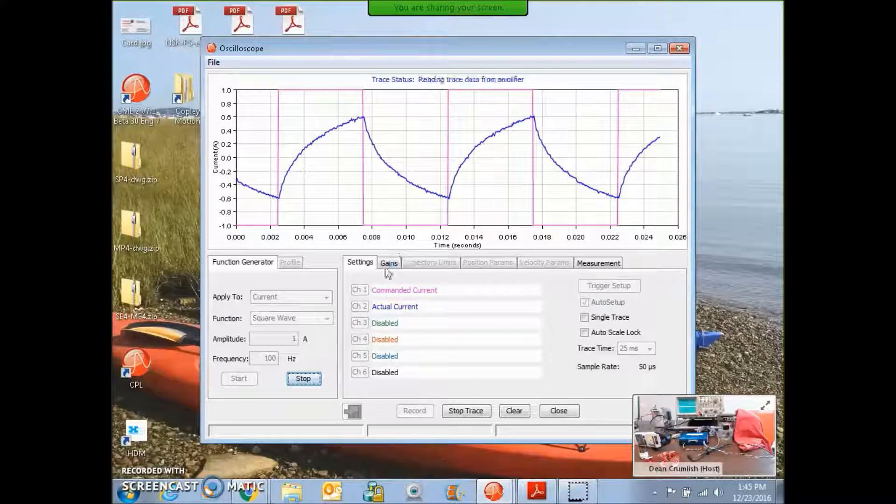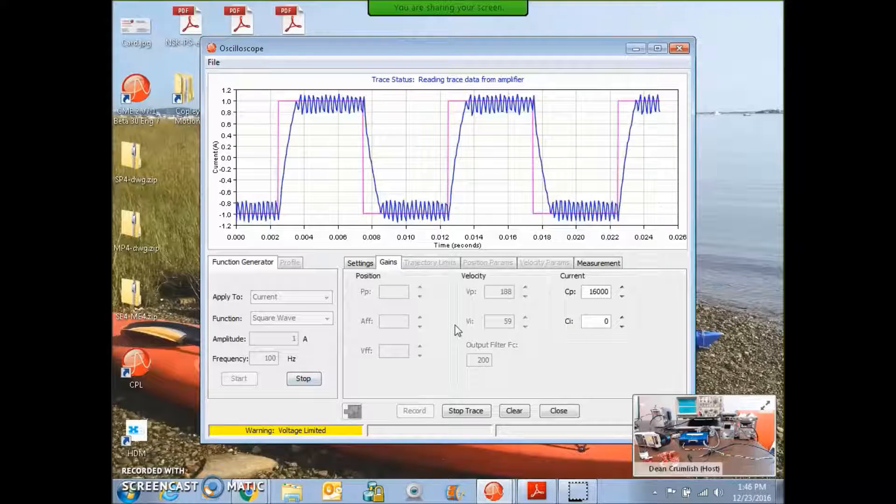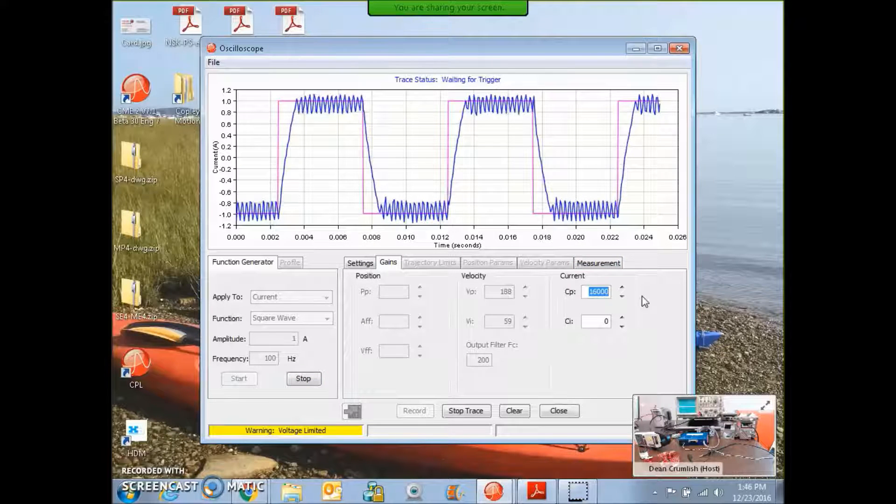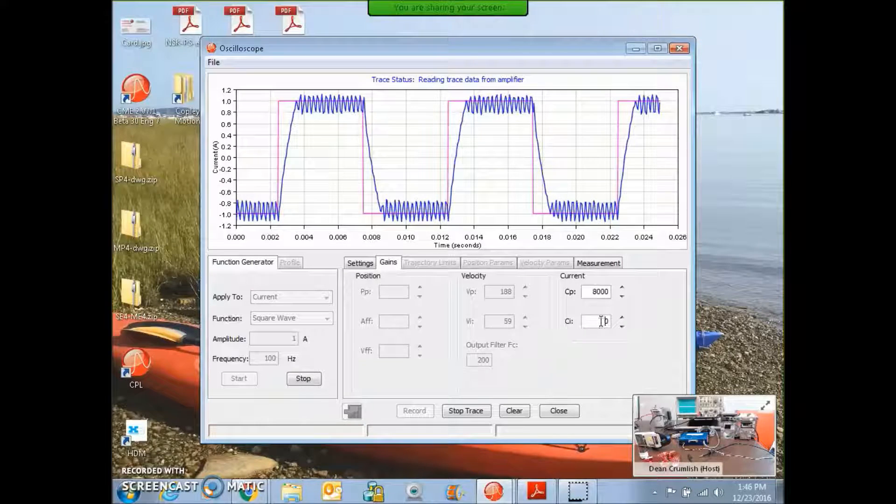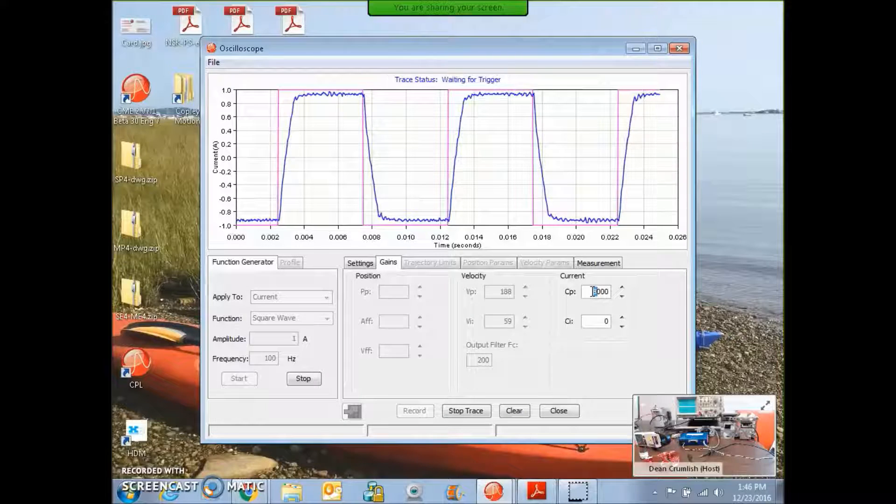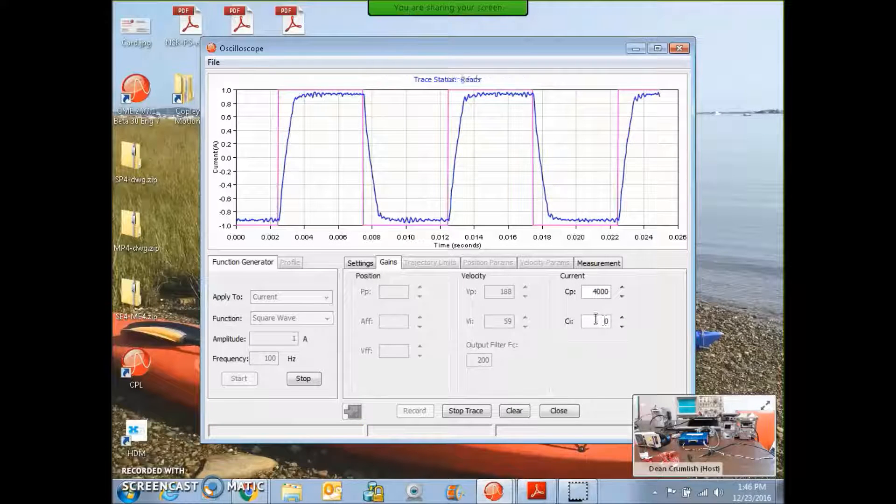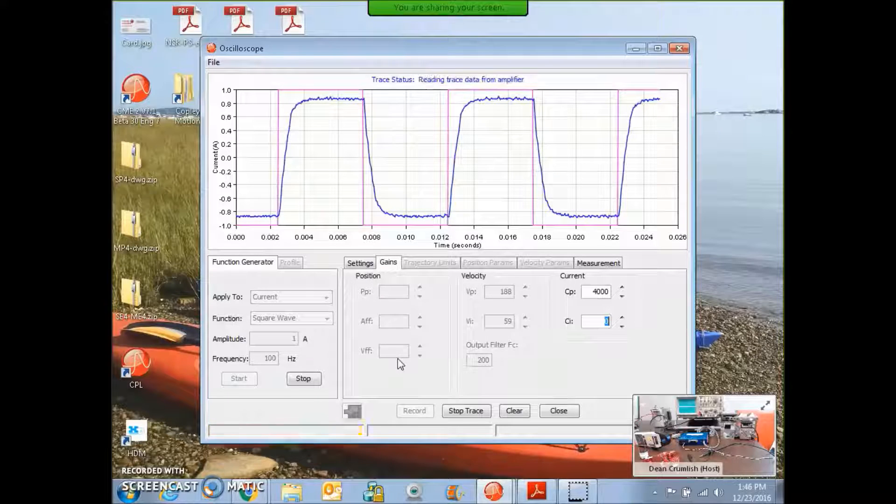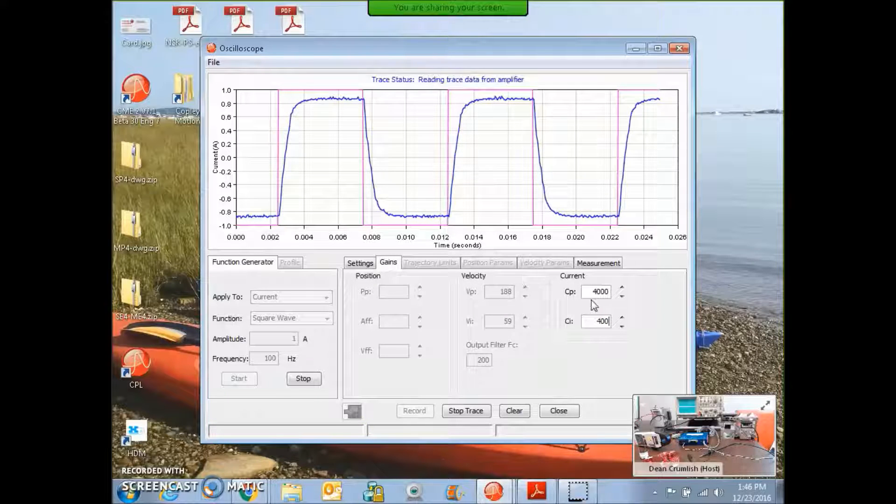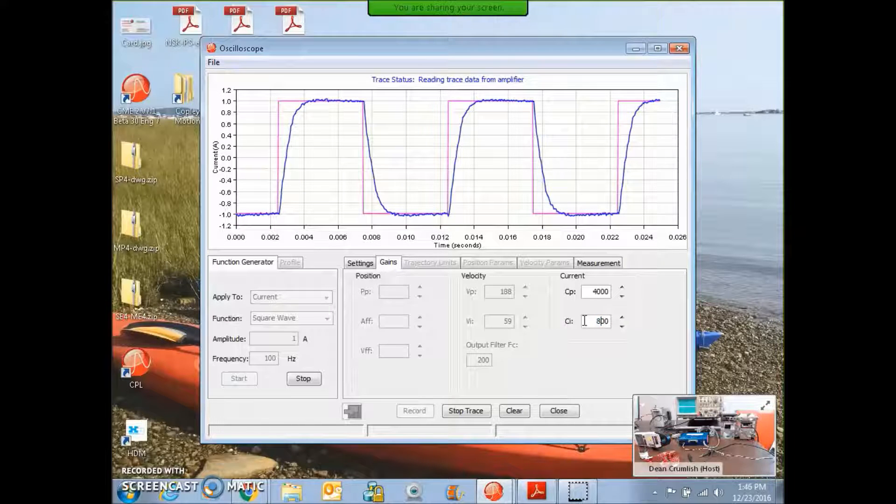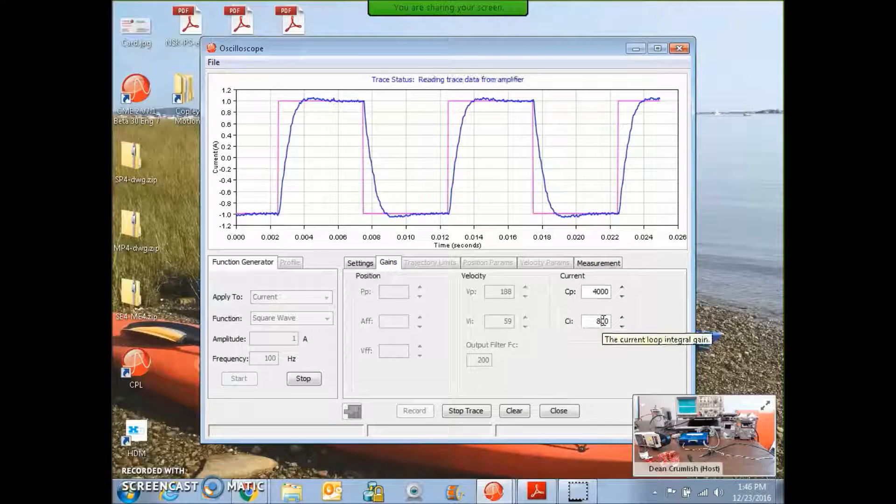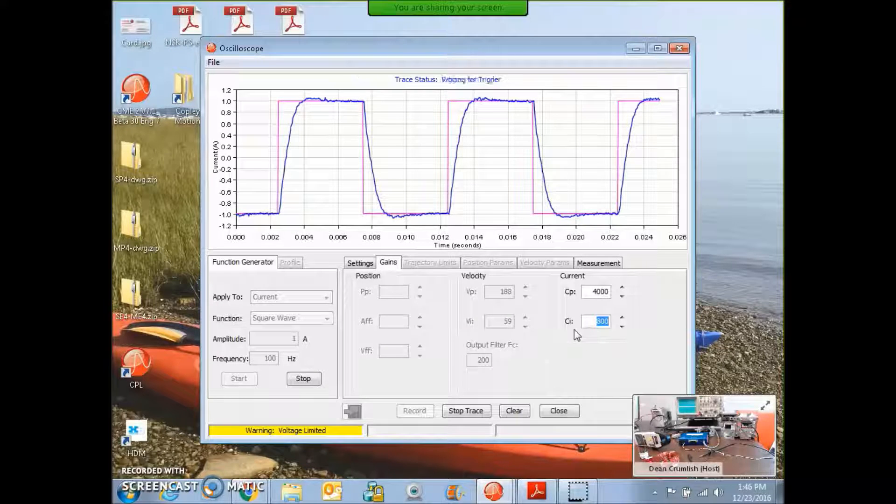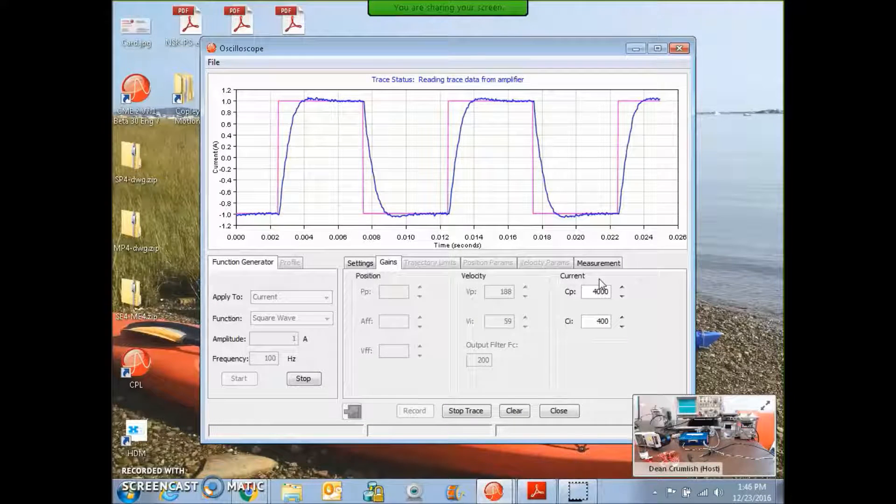That is much more inductance because it's taken longer. So we cranked it up, too much gain. Cut it in half. Still a little buzzy. I'm going to knock it down a little bit there. This is a rather large inductance. And let's give it a little too much integral term to see where that is. There's an integral windup, a little bit of overshoot there. Let's cut it in half.